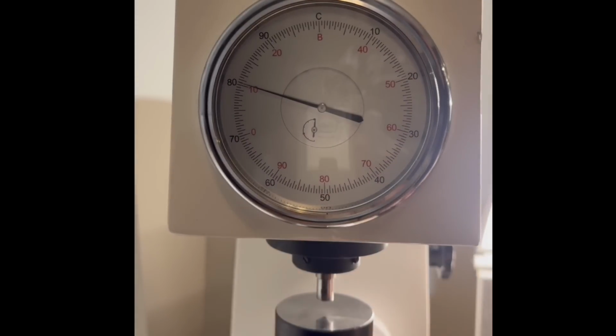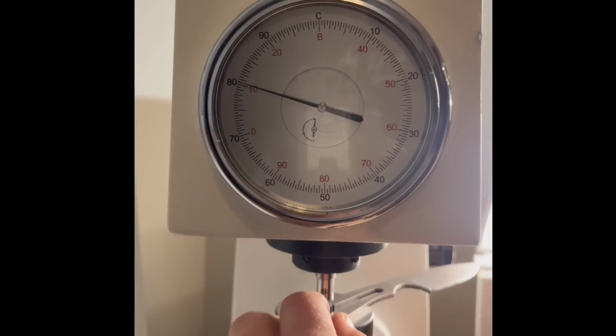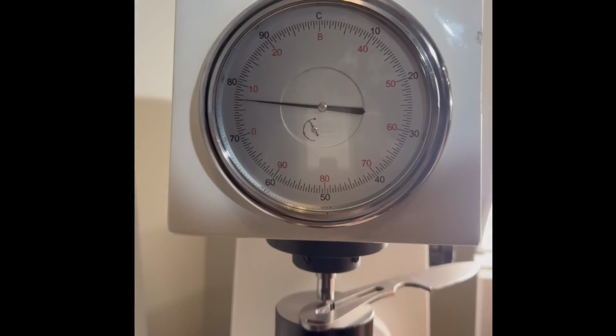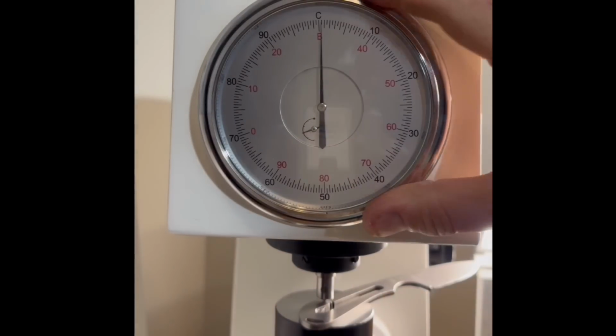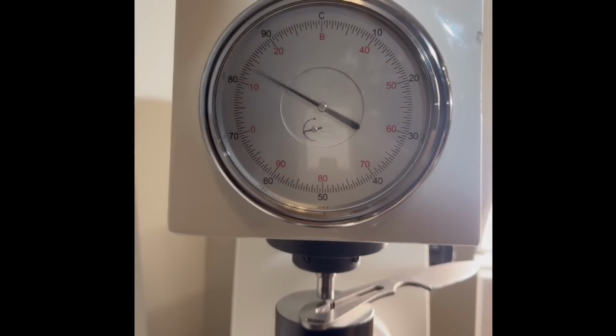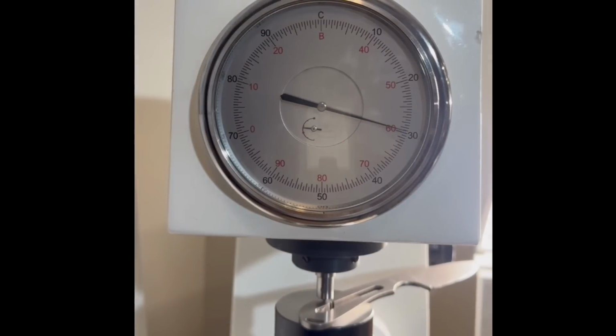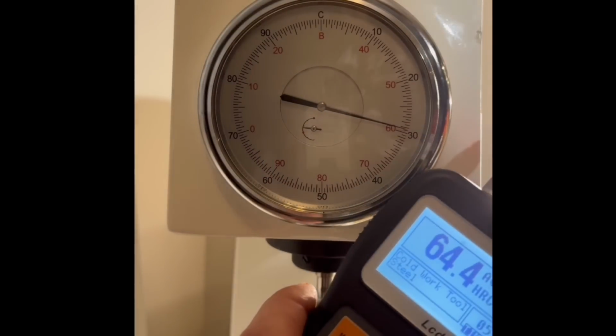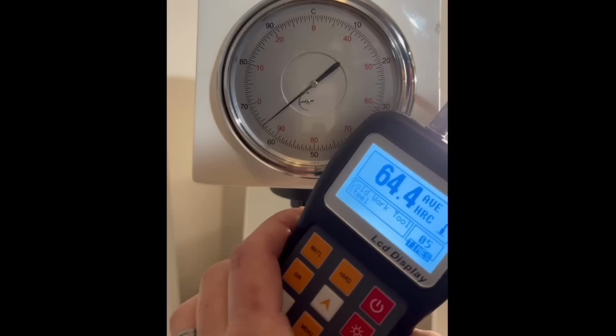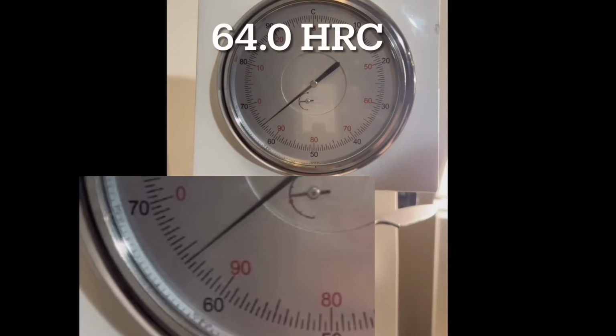I continue by moving the camera back to the benchtop and placing the blade under the probe. And by the way, the video speed is 2x for this segment. The benchtop Rockwell tester calibration video came out recently, and it gets into a lot more detail on how this device operates. I'm holding my breath for 64 plus or minus 1/2. 64, spot on. Unfortunately, not always.